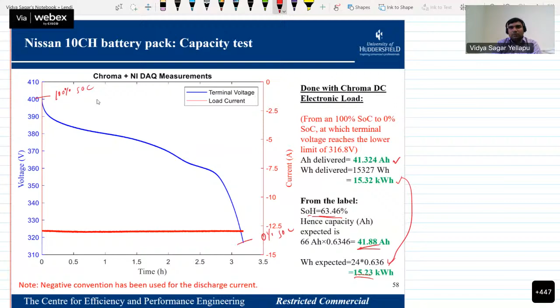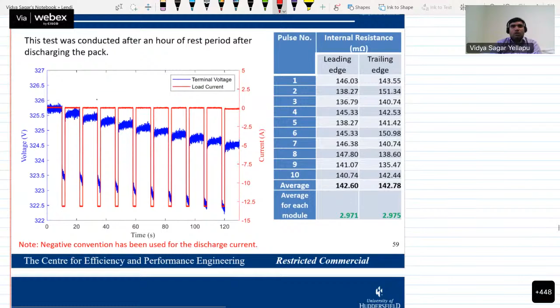Then after that, this is the capacity testing. This is the full voltage, and this is the voltage corresponding to 100% state of charge. This corresponds to 0% state of charge. On this battery, it was labeled that the SOH is 63.46. As per that, the ampere hours expected are 41.88 ampere hours, and the watt hours expected are 15.23 kilowatt hours. From this test, we could find figures close to this: 41.324 ampere hours here, and 15.32 kilowatt hours here, which is close to this one, and this one is close to this one.